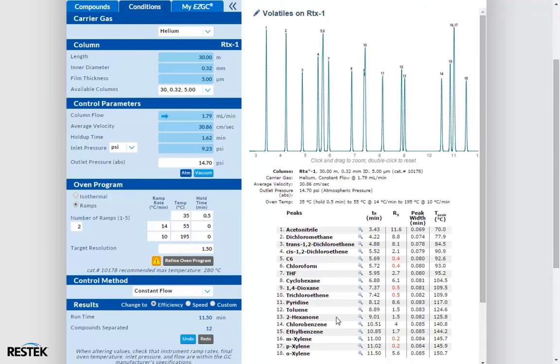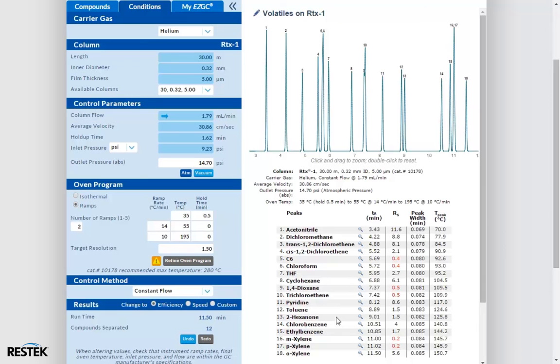So we can see that we've regained the resolution between toluene and 2-hexanone by using the refine button. Generally, when we change between speed and efficiency mode, we can use refine to fix any changes in resolution that occur due to the lack of oven program translation. And one thing to note is that if we were to simply translate the original oven program, we would end up with an equivalent chromatogram as what we started with before switching to efficiency optimized flow, but the total program time would be 15 minutes instead of only about 12.